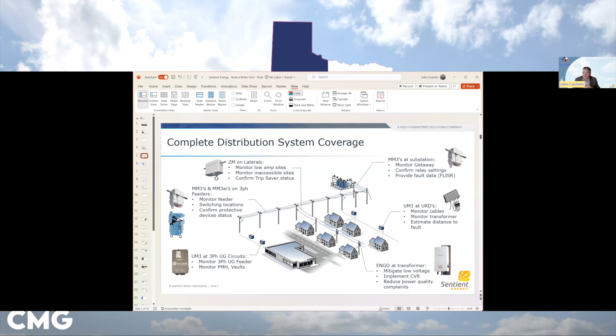Then we have our MM3s and MM3 AIs on three-phase feeders, for monitoring once you get out on the grid beyond the substation. UM3s are for three-phase underground circuits, UM1s for single-phase underground residential distribution. And then we have our ENGO, which will be replaced by our VC10 device, used for grid edge control. We'll talk through that as we go.